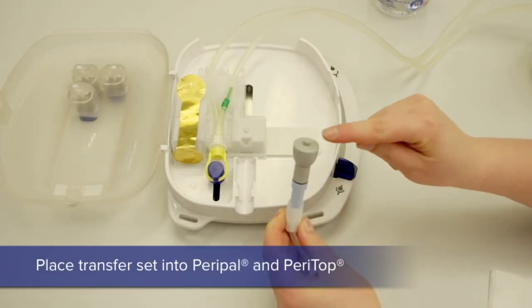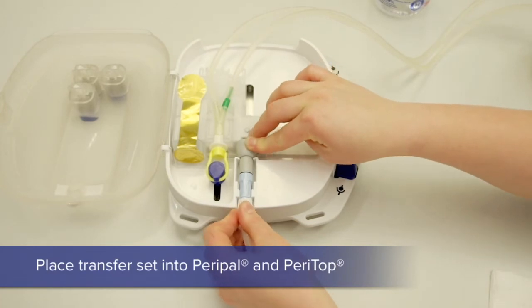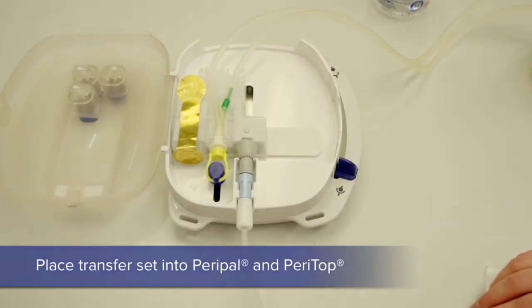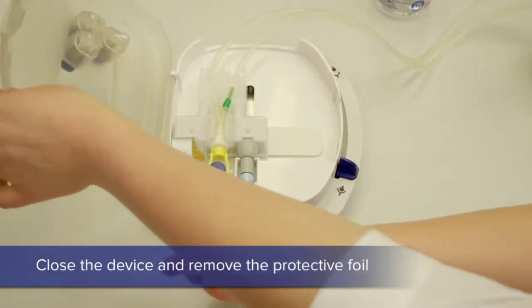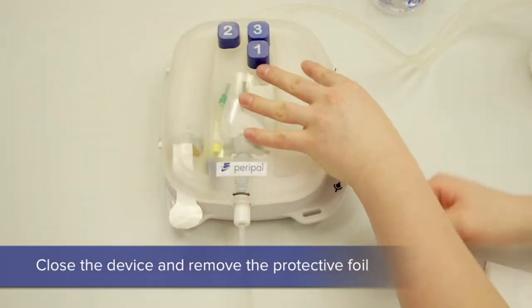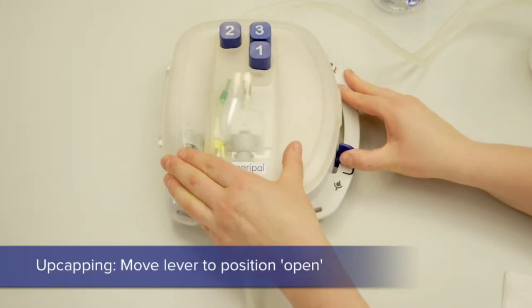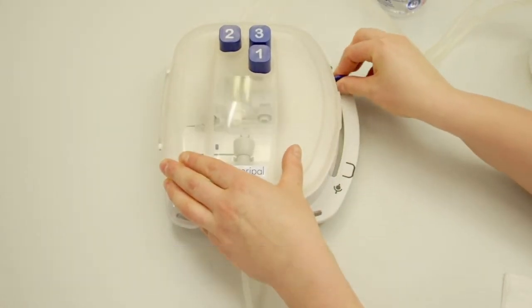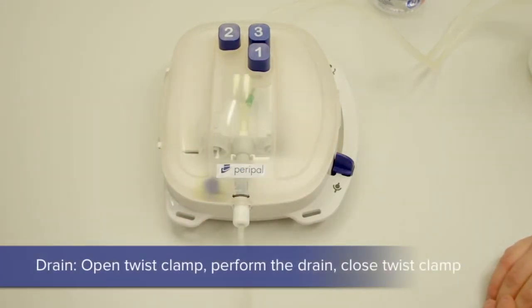The latch is then placed in position. The PeriAdapter is connected to the patient line already and this is placed into its slot in the device. Keep the protective tab outside of the device when closing the cover, and then it is removed safely. The lever is moved all the way to the top and then down. Now we are connected.